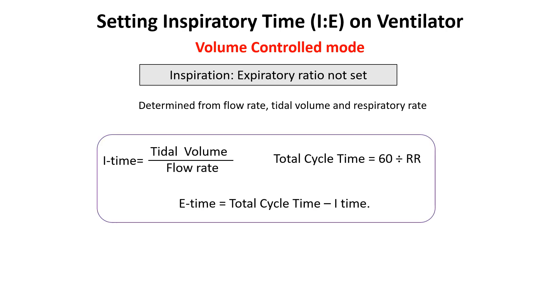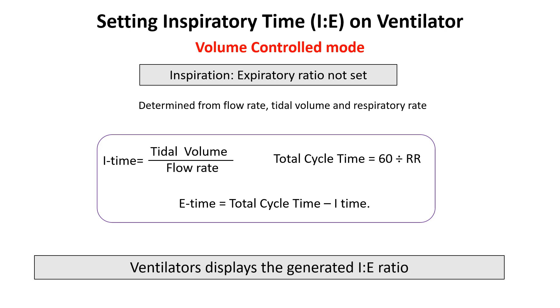In volume-controlled ventilation, we typically don't set the IE ratio directly. Instead, the IE ratio is determined indirectly by adjusting tidal volume, flow rate, and respiratory rate. Since inspiratory time is determined by tidal volume and flow rate, the expiratory time is calculated based on the total cycle time. While volume control ventilation does not allow direct IE ratio setting, you can adjust flow rate, tidal volume, or respiratory rate to achieve the desired ratio. Some modern ventilators may display the IE ratio as a guide when adjusting these settings.